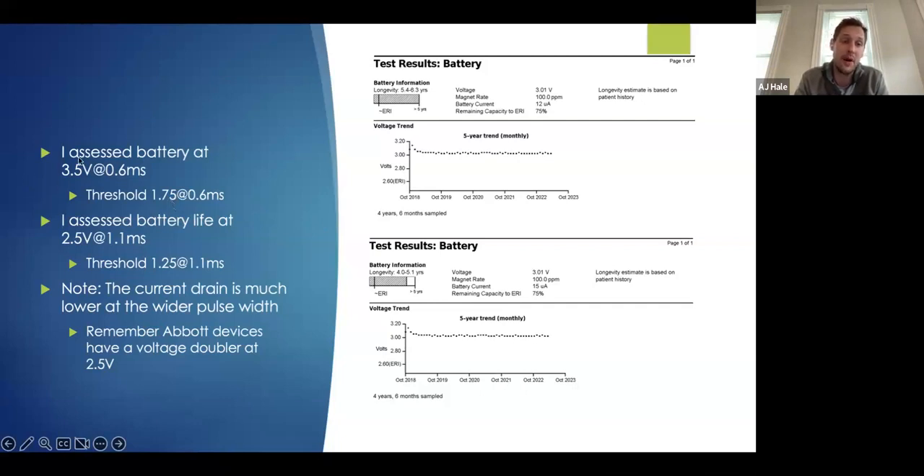If I want a two-to-one margin, we're getting above the voltage doubler in an Abbott device — at 3.5 volts at 0.6, or around 3.2 at 0.6 — which is not exactly great for the battery. You can confirm this by programming the outputs permanently and then going to the battery screen under test results to see the current drain. The current drain for the output showed 12 microamps.